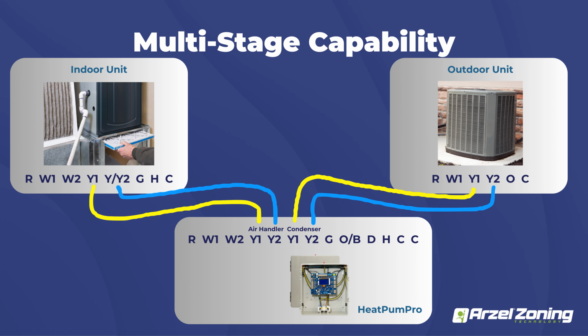So when you guys are doing these wiring, it's a little bit different than most of the panels out there. And you can see in the diagram there, you just want to make sure you separate that out. That's going to handle all the freeze protection and that on the heat pump side of things or the air conditioner, but it also locks out that second stage blower. So you don't have to worry about high stage blower on a really small zone that just can't handle that airflow. So it gives you guys a lot of adaptability so that you can program that panel so that you can be within range of your equipment, but still give that customer satisfaction of their comfort in the areas as well.